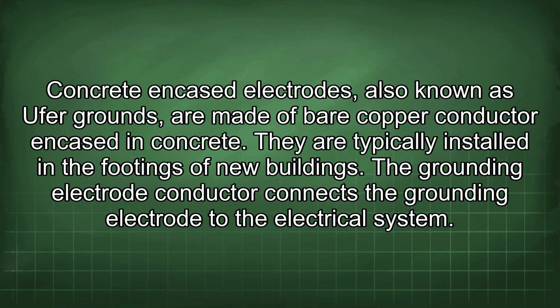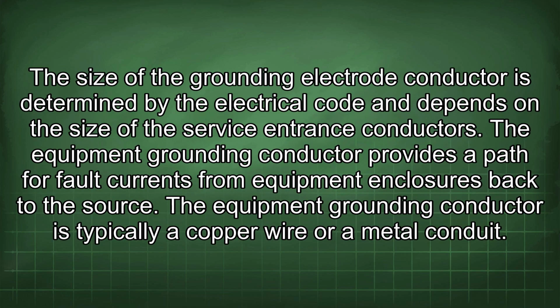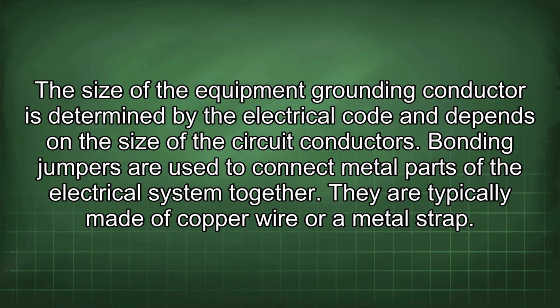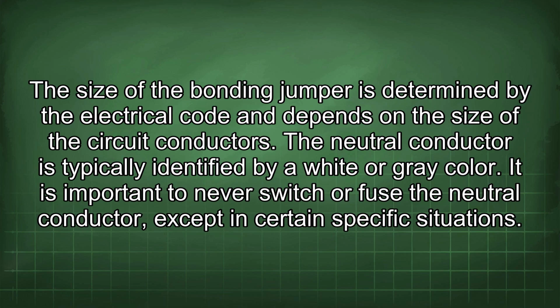The grounding electrode conductor connects the grounding electrode to the electrical system. The size of the grounding electrode conductor is determined by the electrical code and depends on the size of the service entrance conductors. The equipment grounding conductor provides a path for fault currents from equipment enclosures back to the source. The equipment grounding conductor is typically a copper wire or a metal conduit. The size of the equipment grounding conductor is determined by the electrical code and depends on the size of the circuit conductors. Bonding jumpers are used to connect metal parts of the electrical system together. They are typically made of copper wire or a metal strap. The size of the bonding jumper is determined by the electrical code and depends on the size of the circuit conductors.